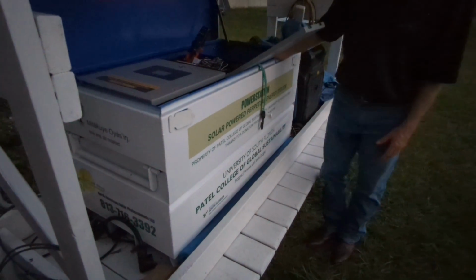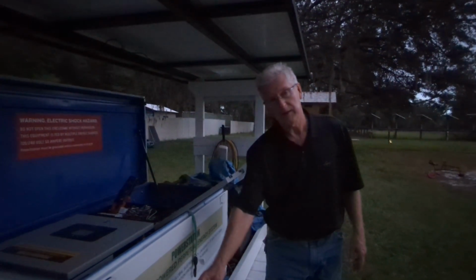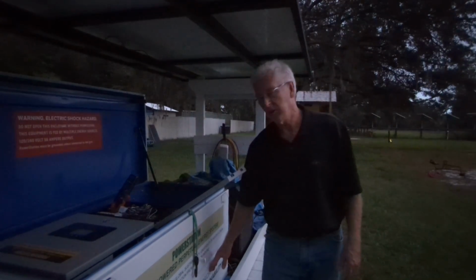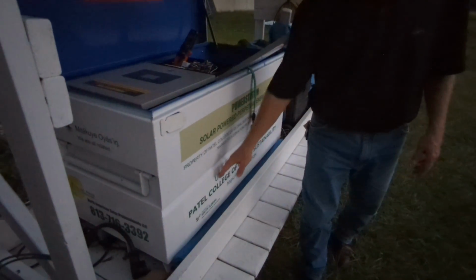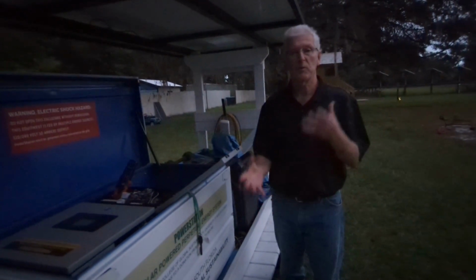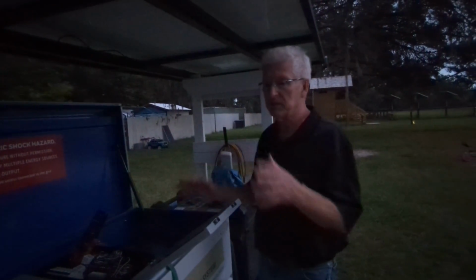There's room. If we put the auto transformer in here, I'm hoping it's not any wider than a battery. So that means now you wouldn't have capacity for 20 kilowatt hours. You've got 10. We're hoping you would have enough for 15 in the future, plus your auto transformer. So you get 50% more autonomy, plus your auto transformer to balance your loads. Unless it's small enough and comes in a waterproof casing and could be put here. You could put the auto transformer outside, but I prefer all your AC voltage to stay in the box, because everything's bonded, everything's grounded, nothing is accessible to someone else.